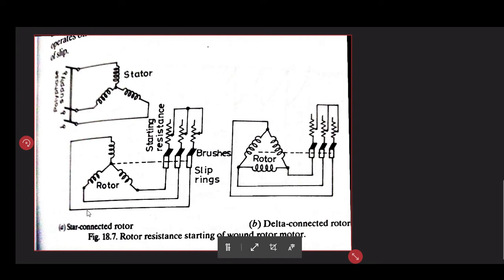energy saving during normal run, because in normal running condition your rotor will behave like the rotor of a normal squirrel cage induction motor with small resistance value, but during start you can offer a huge starting resistance, thereby you can have an improved starting torque and reduced value of starting current. And both are interrelated, not proportional, but both are interrelated.